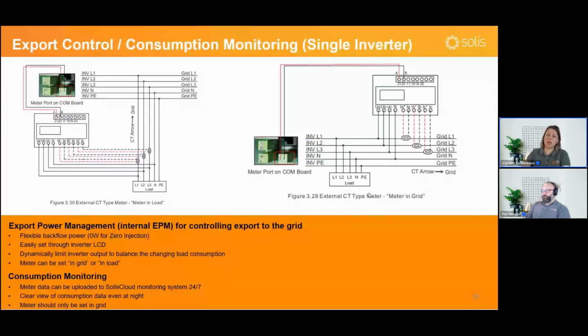Also, the location of the meter can vary. You can install this meter either on the load side, so it will measure what the loads are consuming, and based on that, the inverter will try to match it. For example, if you have a zero export scenario and you have set zero backflow power for the inverter, the inverter will match its generation with the actual load consumption. This is when you have the meter set in load.